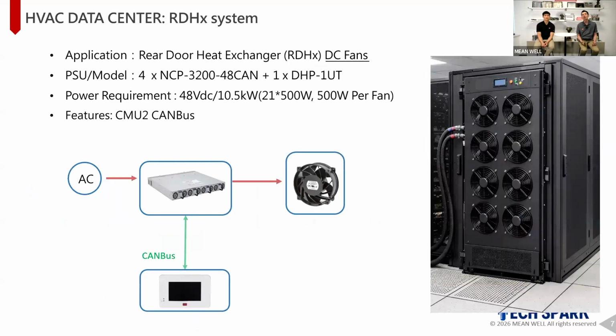Another application we've seen is for the rear door heat exchanger DC fan. This customer uses our rack power to power the fan. Every rear door heat exchanger has about 8 fans on it, and the customer uses rack power across multiple racks to power multiple rear door heat exchangers. Imagine one server rack, 30U or 42U, has one rear door heat exchanger attached. If you have 50 of them, you have 50 rear door heat exchangers with a lot of DC fans running inside, and the rack power is basically to power those fans to pull the heat out of the server rack.